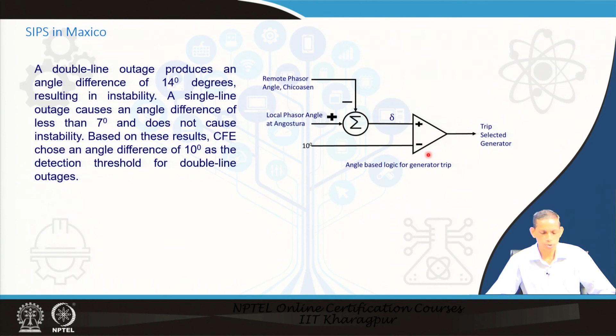So, once the generating station reduces generation or the generators are out, the stability of the system can be retained, and the cascading trippings can be avoided. So, this gives a systematic protection scheme using phasor measurement units at remotely placed PMUs.